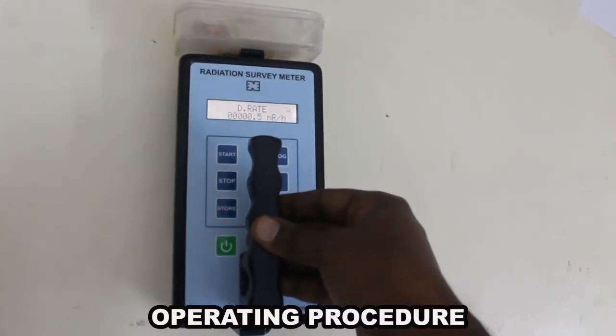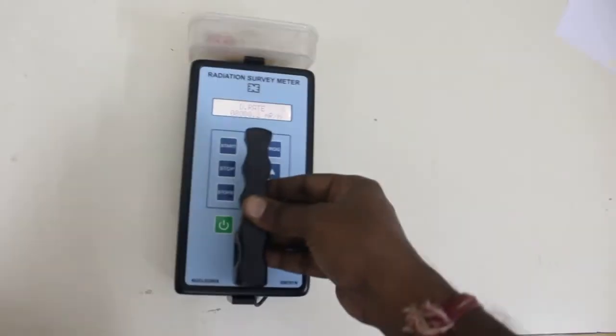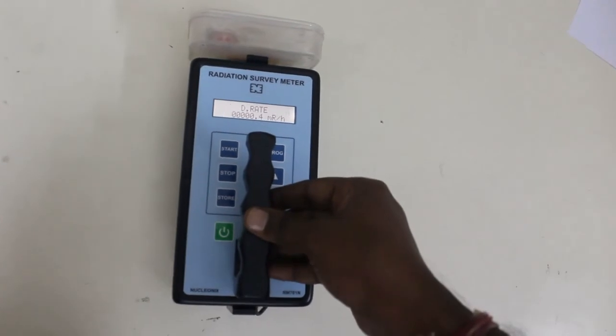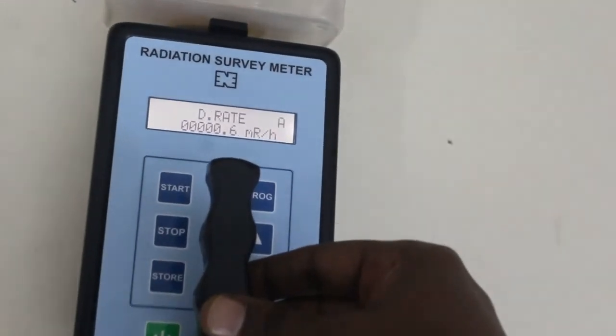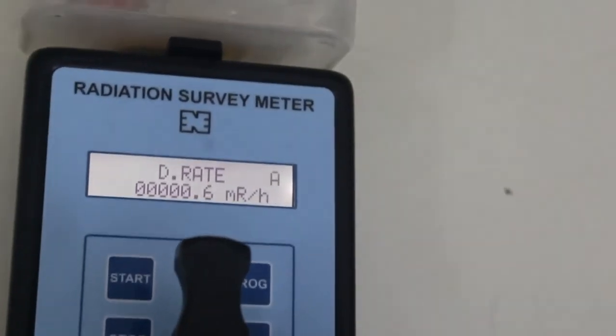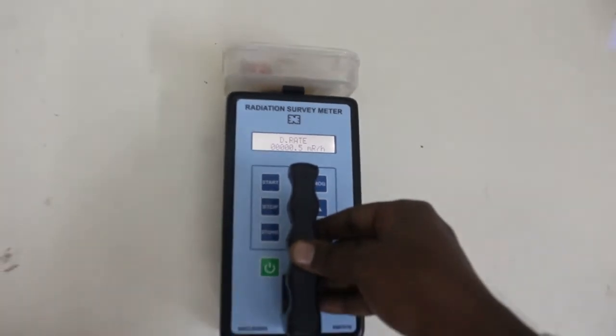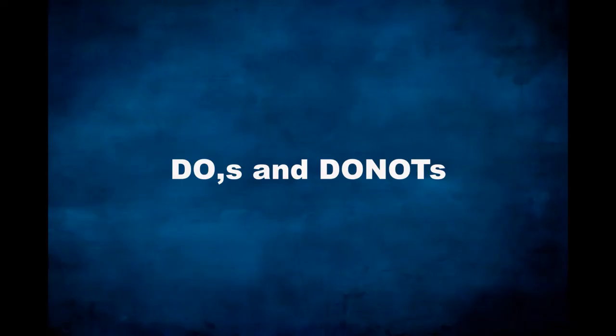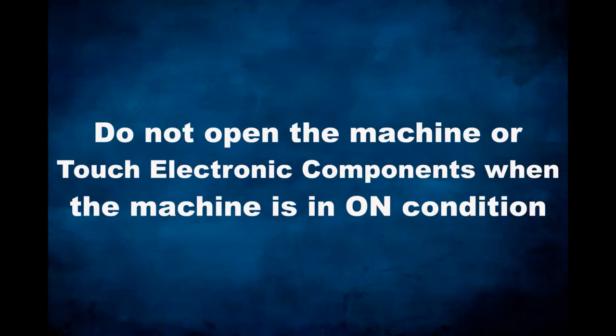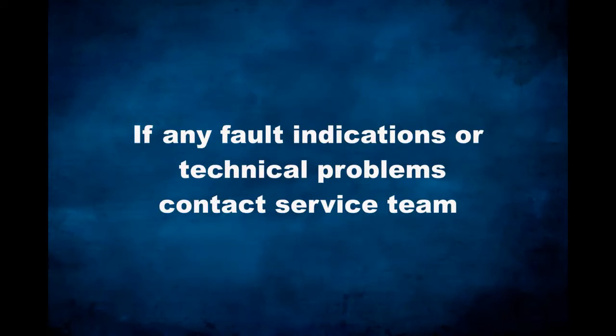Operating procedure: this unit is given to you in ready-to-use condition. On unpacking, the user is advised to go through the instruction manuals. The user can operate the equipment to make measurements in CPS, CPM, and dose rate modes as per requirement. The user can also store data readings if required, and recall the data using the software provided at an extra cost. Do not open the machine or touch electronic components when the instrument is in the on condition. Replace batteries when needed. If fault indications are visible on the display, please contact our service team.